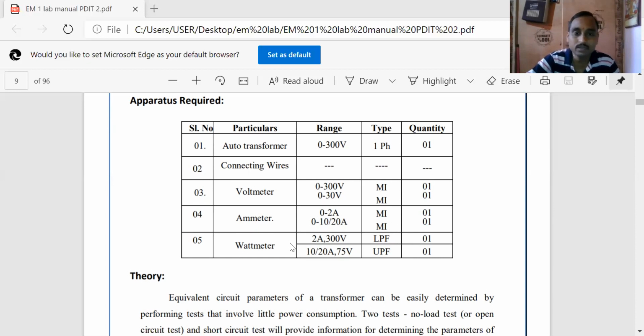And wattmeter: there are two types of wattmeters. One is the low power factor wattmeter and the other is the unity power factor wattmeter. For the no load test, or open circuit test measurement, we have to use the low power factor wattmeter. On that wattmeter it is displayed as cos phi equal to 0.2. That is called a low power factor wattmeter. The range is 2 ampere and 300 volt.